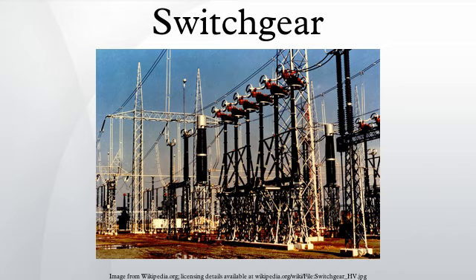Classification: several different classifications of switchgear can be made. By the current rating: by interrupting rating, circuit breakers can open and close on fault currents. Load break, load make switches can switch normal system load currents. Isolators may only be operated while the circuit is dead, or the load current is very small. By voltage class: low voltage, medium voltage, high voltage, extra high voltage, ultra high voltage. By insulating medium: air, gas, oil, vacuum, carbon dioxide.